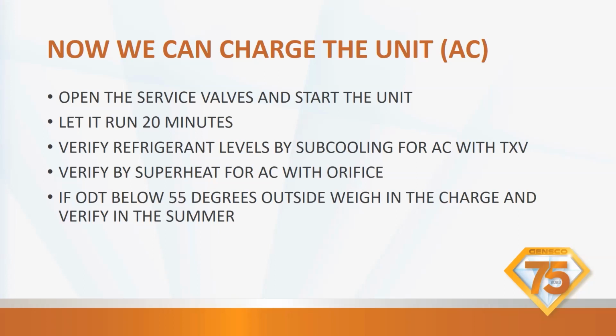you're going to want to verify that that unit actually has a charge. All you have to do is take the cap off. Take your pen or your tweaker screwdriver and just push in on the Schrader valve just momentarily, just to see if it goes. If it does, you know you have refrigerant in it.